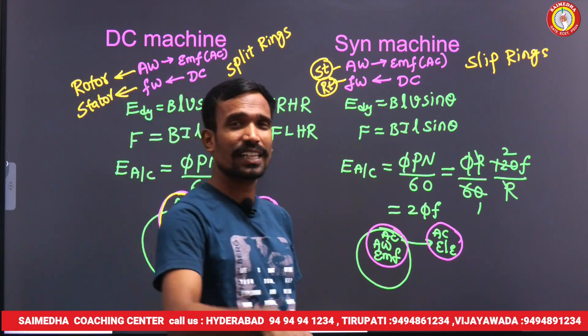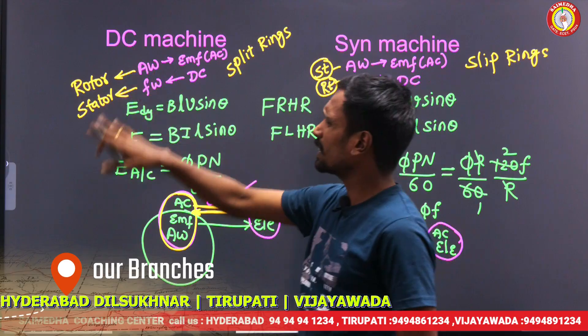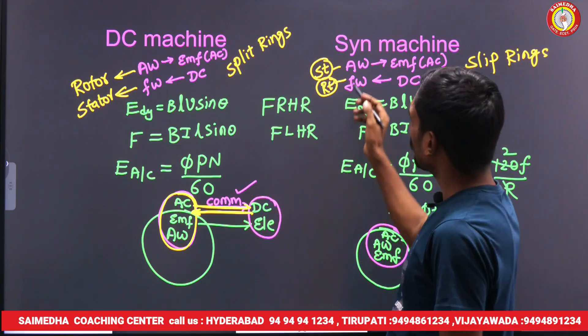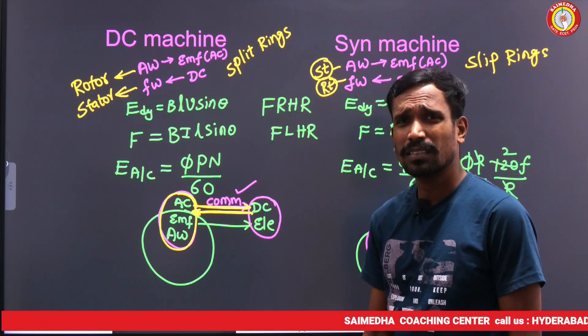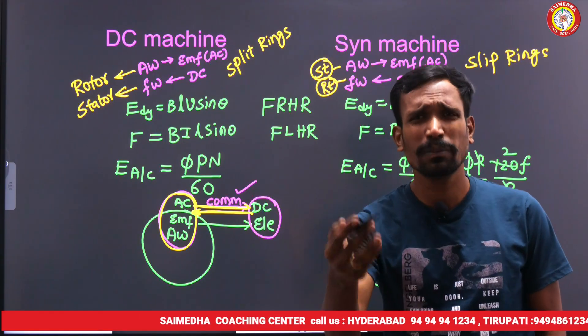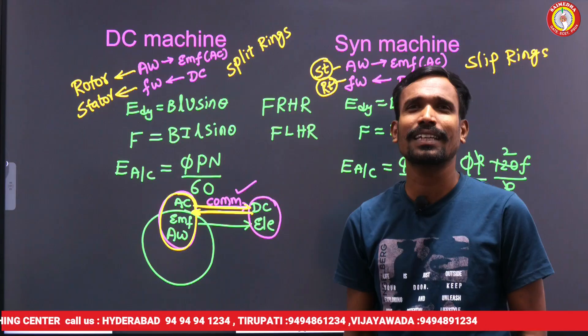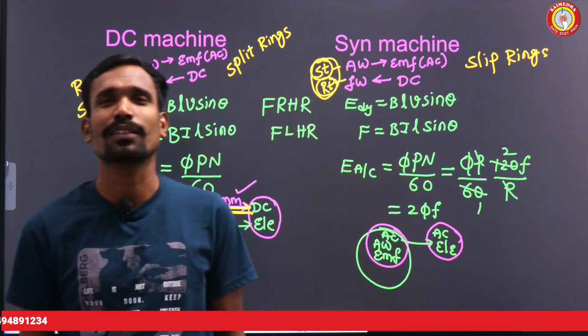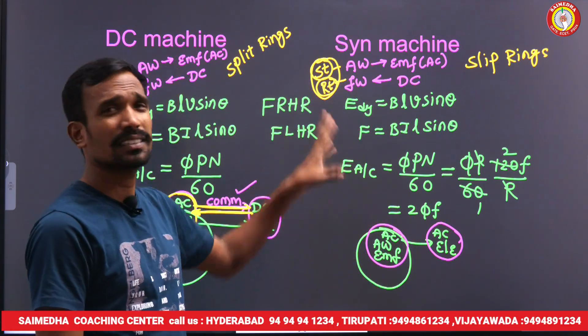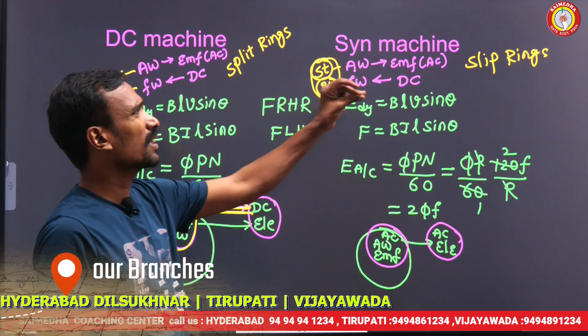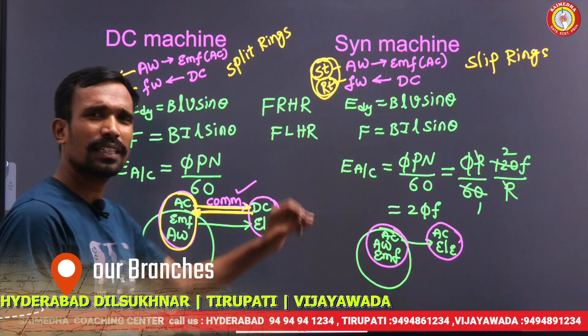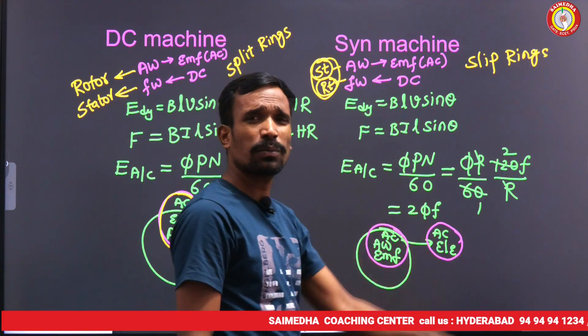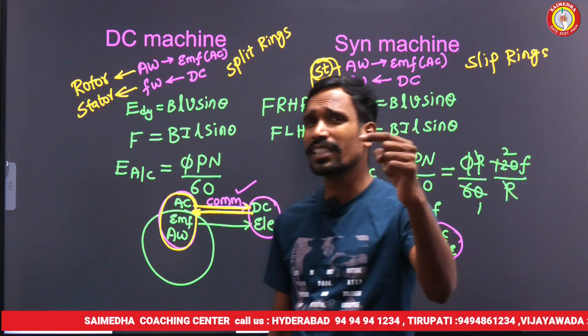If the armature is placed on the rotor, the field winding should be on the stator. That possibility is there. But stationary armature is preferable for high-rating applications. You can use a rotating armature for low-rating applications. In summary: synchronous machines use slip rings; DC machines use split rings and a commutator. Since the commutator is a rotating part, the armature must be on the rotor in DC machines. In synchronous machines, no commutator is needed, so the armature can be placed on the stator.